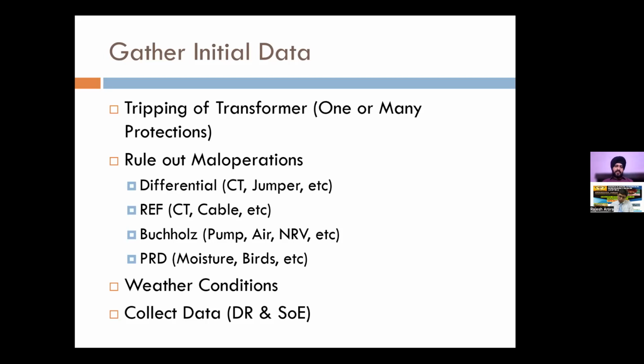You also need to correlate the data from your disturbance recorders, the sequence of events. A disturbance recorder will give you an idea: if there has been a rise in current, then that means there is some fault in play. But if there is any tripping without any rise in fault current, or rise in even normal current, then you can suspect that the fault lies elsewhere.